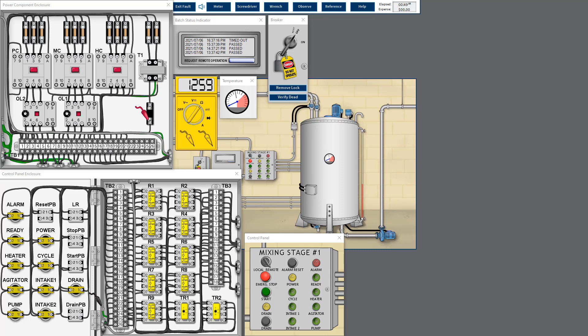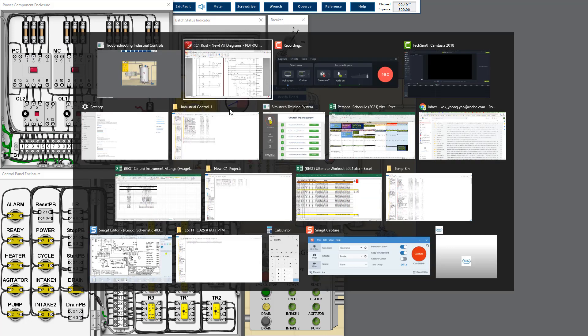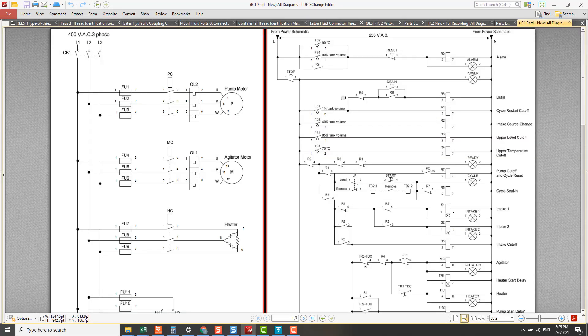In this case there's a resistance reading, which means there's an earth fault — whether before the load, at the load, or after the load. To troubleshoot this earth fault, the easiest way is the divide and conquer strategy.